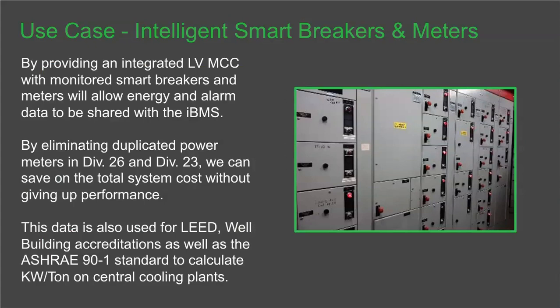We're starting to see now, just like technology in the building space, that intelligence on the power side is also becoming very intelligent, down to even the breaker level nowadays - not only breaker status, but breaker monitoring of KWH. So when you get to that level, we're looking at more intelligent MCCs than we've ever had before.